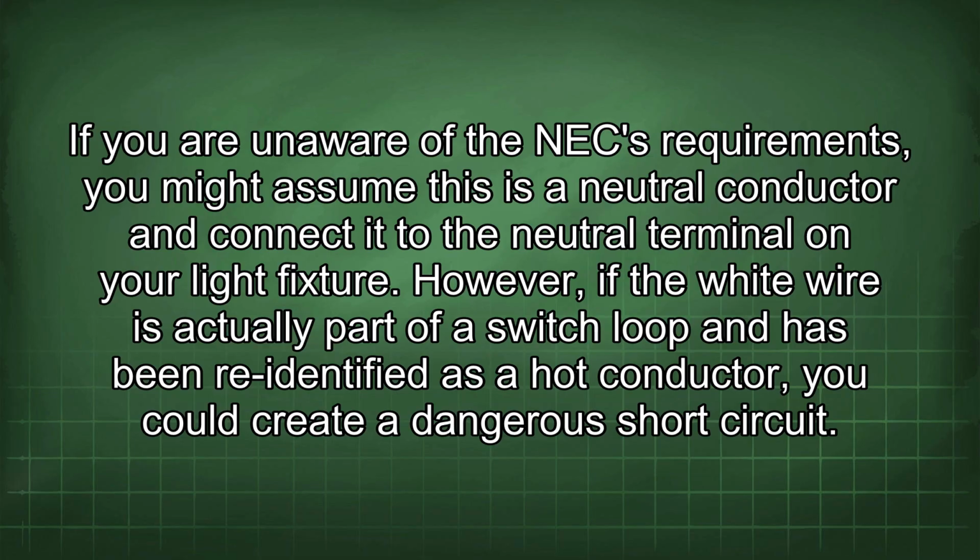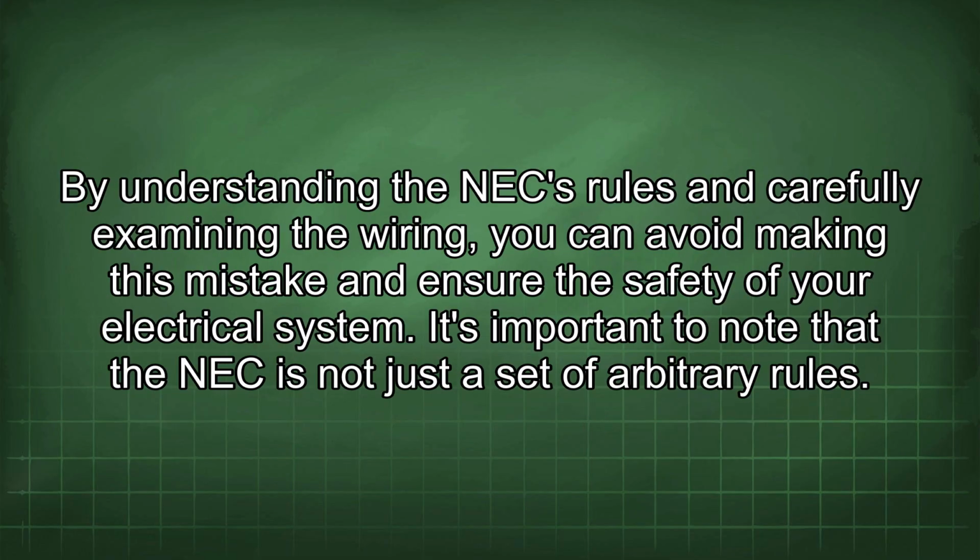If you are unaware of the NEC requirements, you might assume this is a neutral conductor and connect it to the neutral terminal on your light fixture. However, if the white wire is actually part of a switch loop and has been re-identified as a hot conductor, you could create a dangerous short circuit.